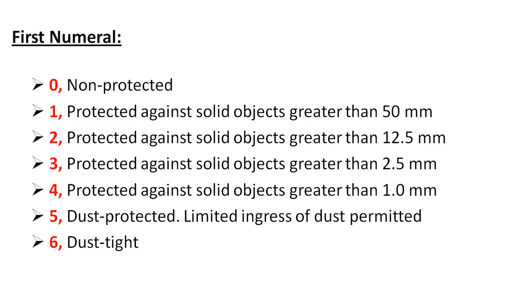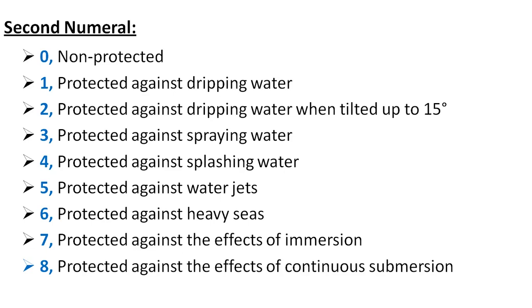Five indicates dust protected — a limited ingress of dust is permitted without having any effect on the operation of the equipment. Six indicates dust tight — no ingress of dust is permitted. That covers all values for the first numeral, which indicates protection against solid foreign objects.